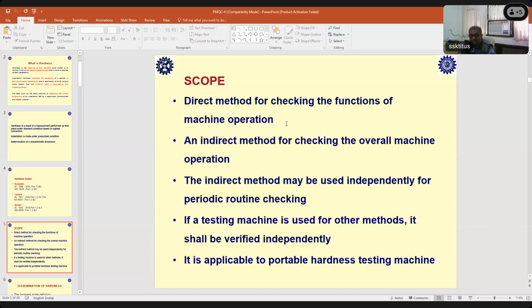And for indirect calibration, we can use the reference material. Reference material means the standard hardness blocks which are calibrated by an NMI or by accredited labs. Even now in India we have several accredited labs which have standard blocks, and we can take those blocks and check indirectly whether the machine is giving results as per the specification laid down in the standard. The indirect method may be used independently for periodic routine checking, because if you want to always keep a check on your hardness measurement, then you have to keep checking the machine and its performance.